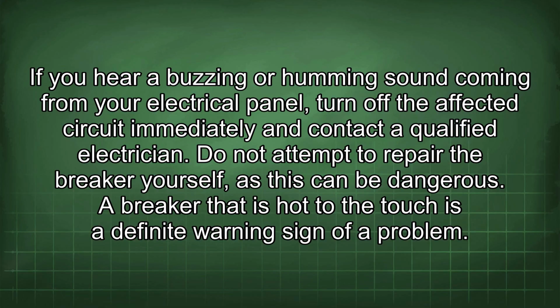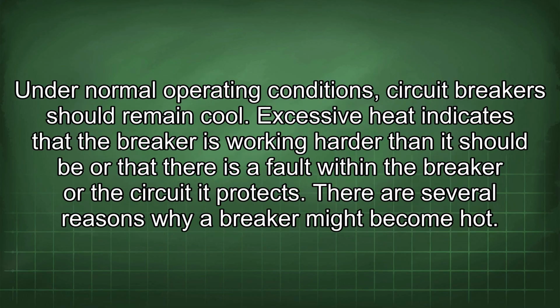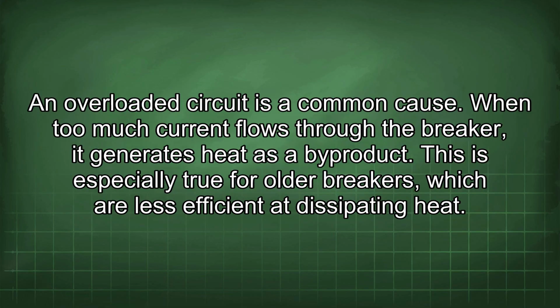A breaker that is hot to the touch is a definite warning sign of a problem. Under normal operating conditions, circuit breakers should remain cool. Excessive heat indicates that the breaker is working harder than it should be, or that there is a fault within the breaker or the circuit it protects. There are several reasons why a breaker might become hot. An overloaded circuit is a common cause.